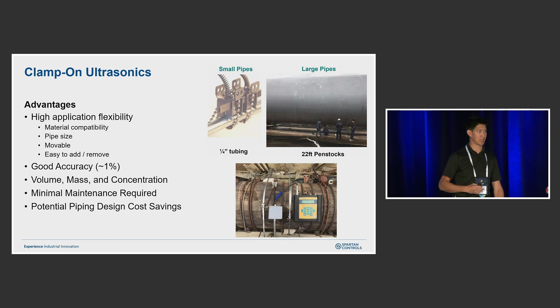Okay, it's not all sunshine and rainbows, and I'm not here to tell you it works in every situation. So one thing is if you want accuracy for, say, custody transfer applications, clamp-on ultrasonic's not really the technology. Okay, that's what magnetic flow meters are probably better suited for. Not that you guys have this, but if you have any sort of steam type applications, that would be a limitation. If you have a lot of solids, and I'm talking about it's probably more solid than liquid, then we can run into some issues there with clamp-on ultrasonics.